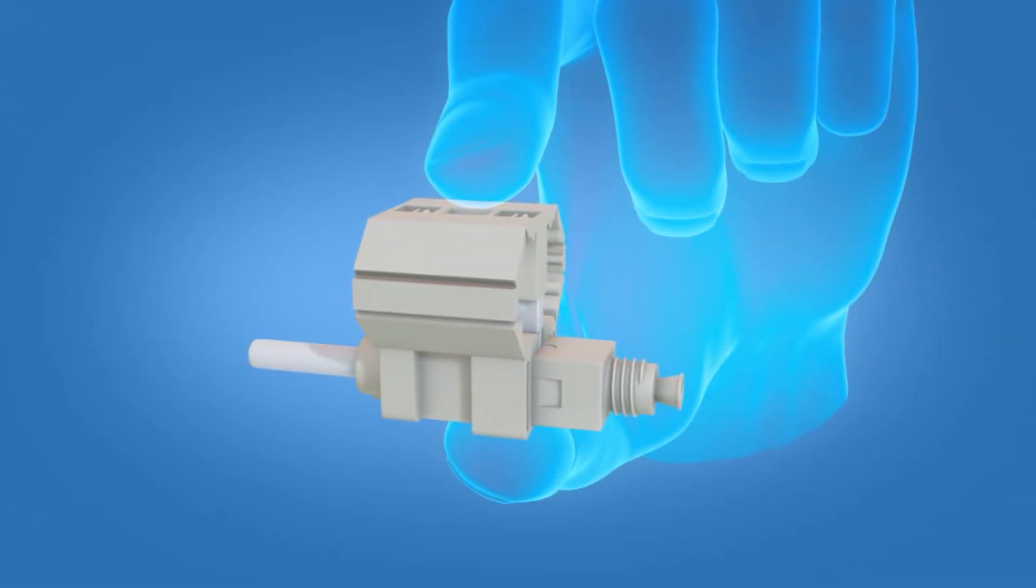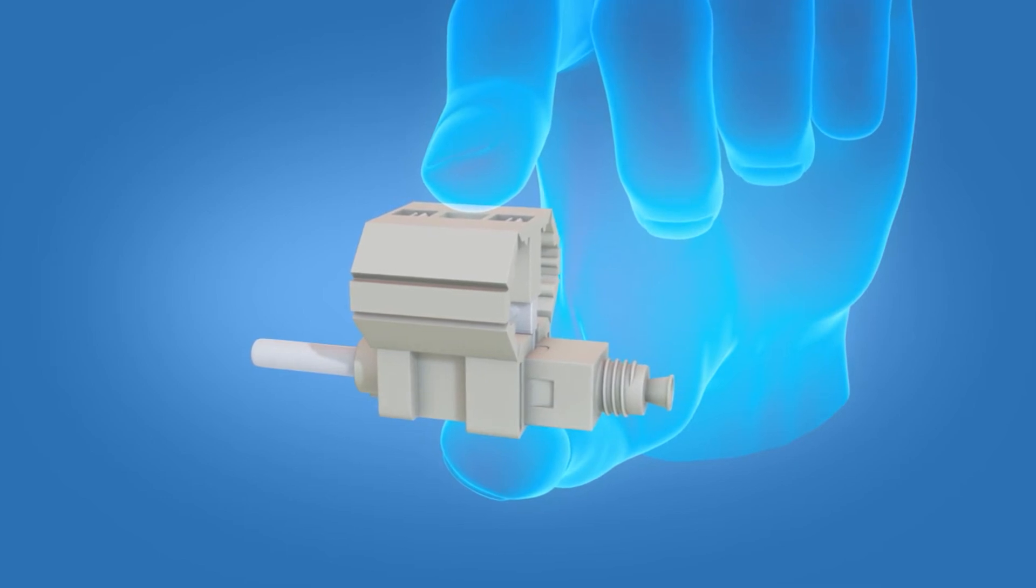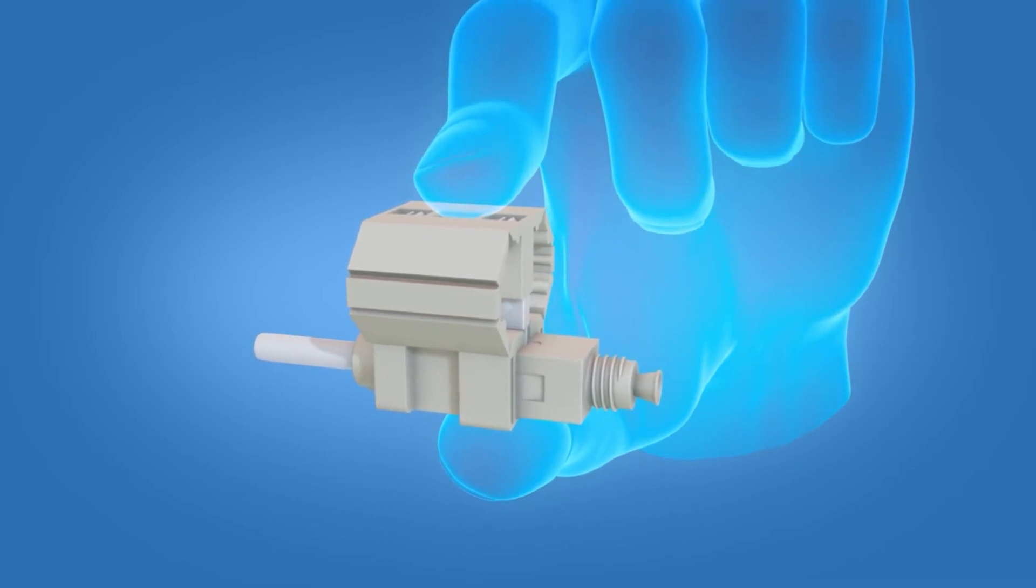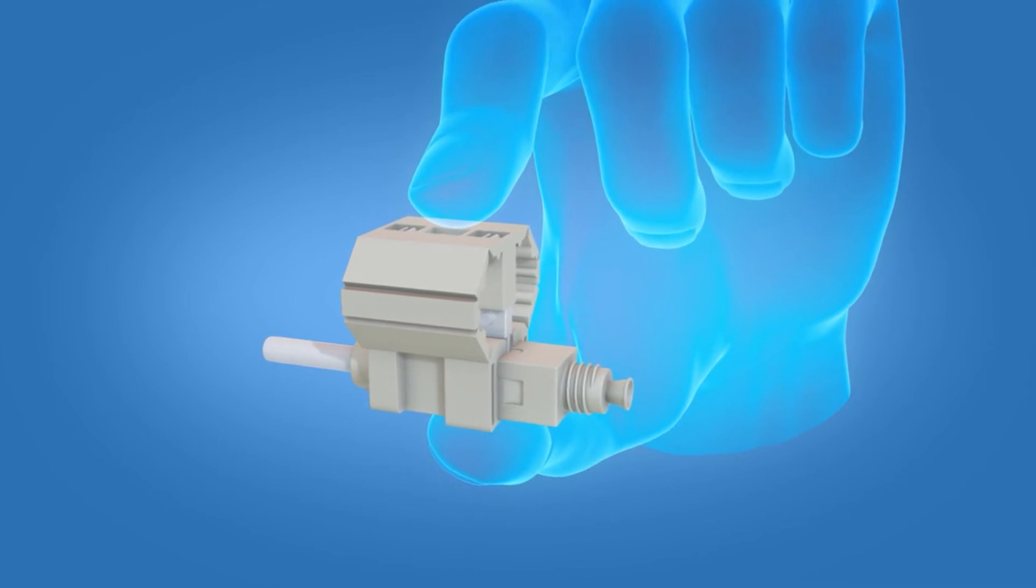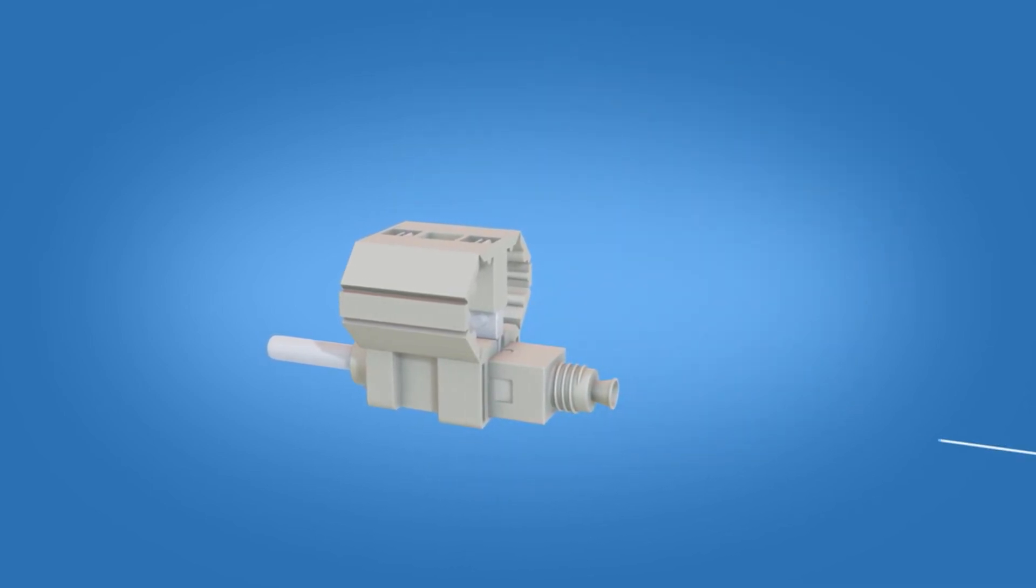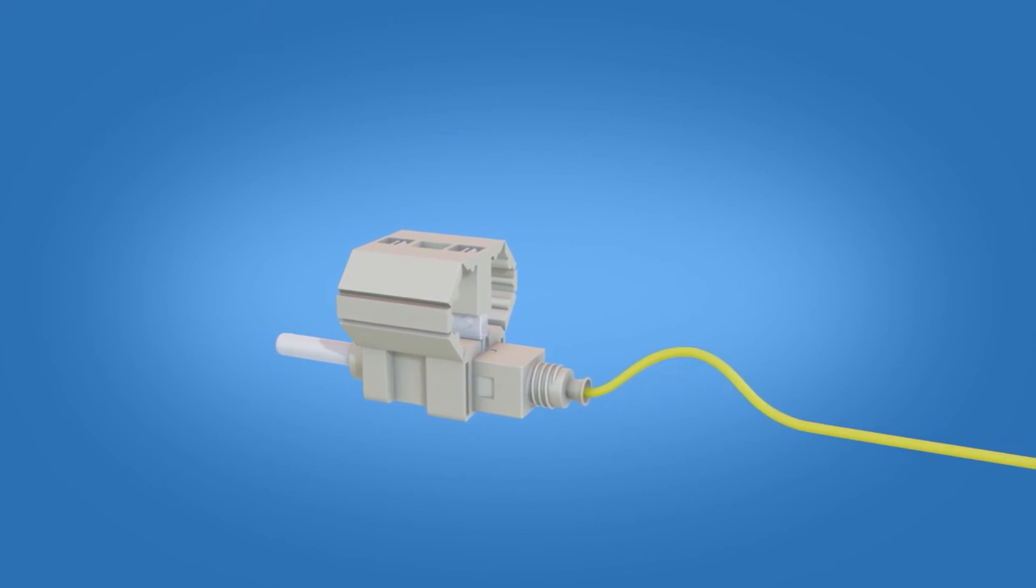Next, take the FastST connector and squeeze the top and bottom of the wedge to ensure that it is engaged. Insert the fiber into the connector. Create a slight bend to maintain contact.